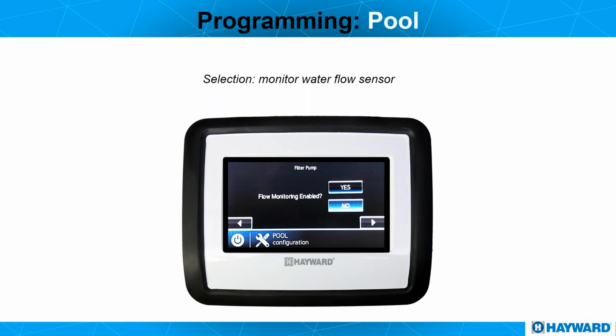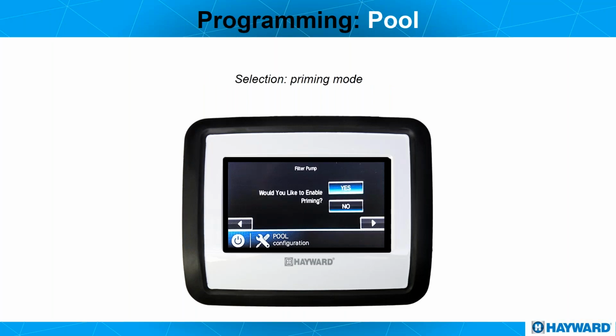Flow monitoring: we can install a flow sensor and choose yes here. That way, if our pump for some reason does not come on but the system thinks it's on, the sensor, since it's not closing, will send a signal saying there's definitely no flow. It's a safety thing.